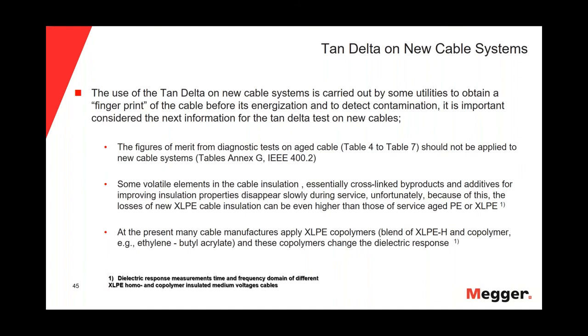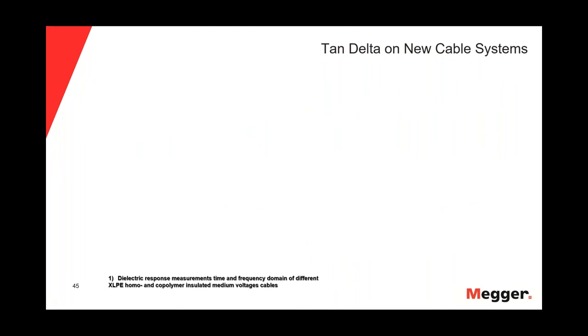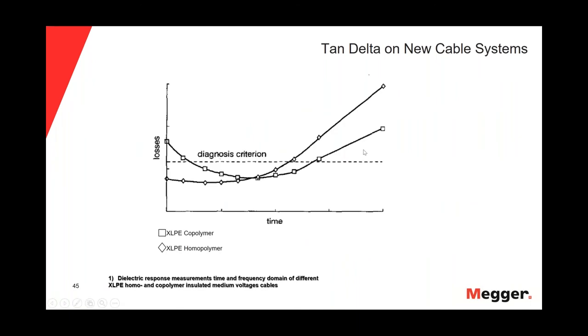These co-polymers change the dielectric response. The next chart shows that for the XLPE homopolymer, the behavior is more or less what we expect — as the cable ages, the tan delta values increase. But for the XLPE co-polymer, even when the cable is new, we will have very high losses, and that loss will be even higher as the cable enters service. So we can get confused if we are not aware of this information.